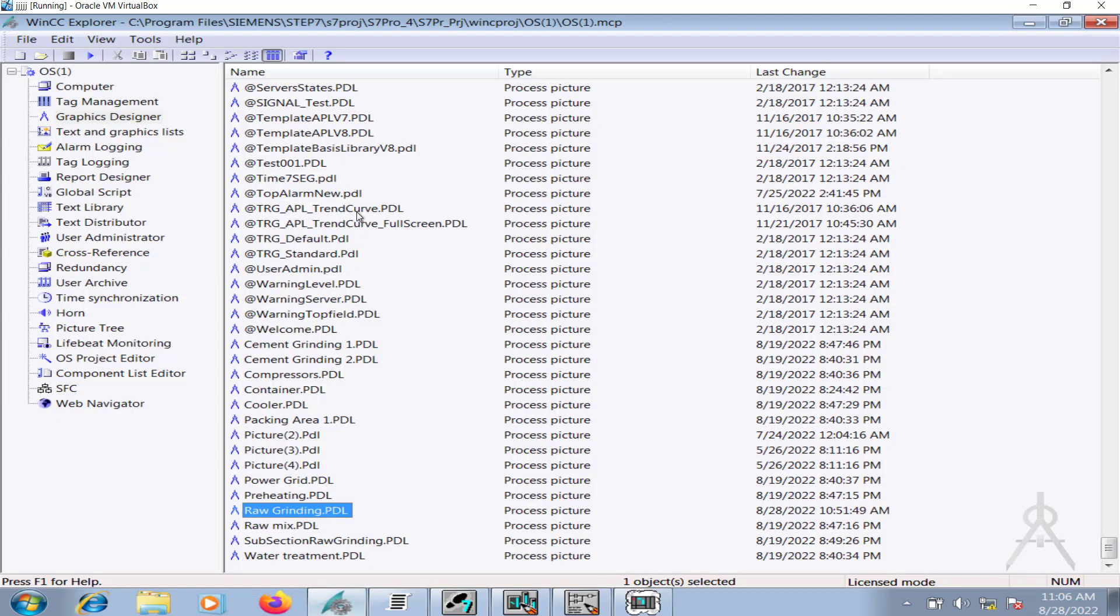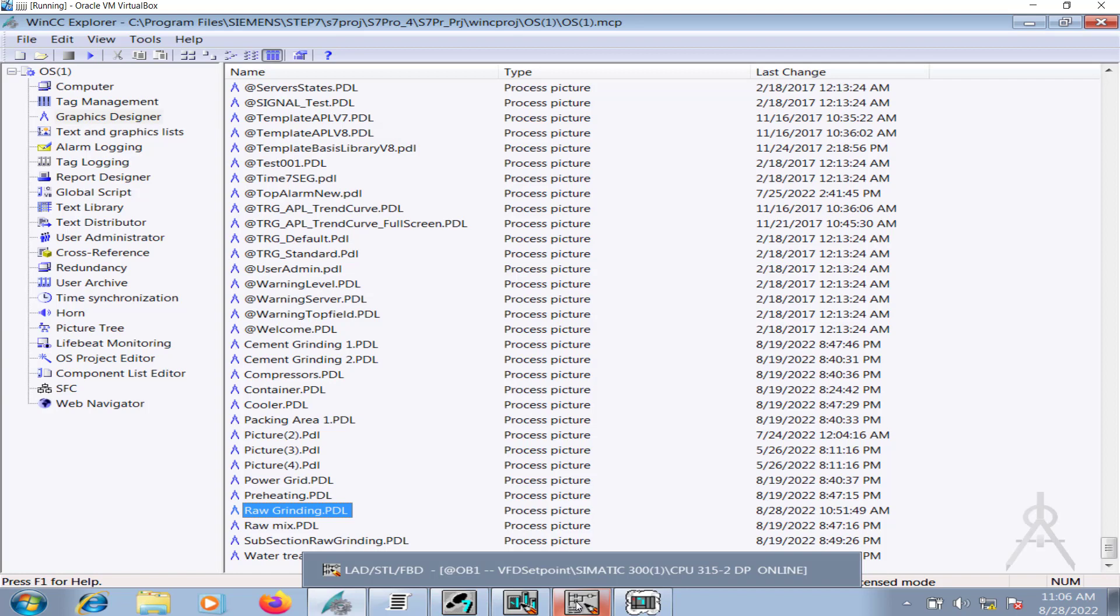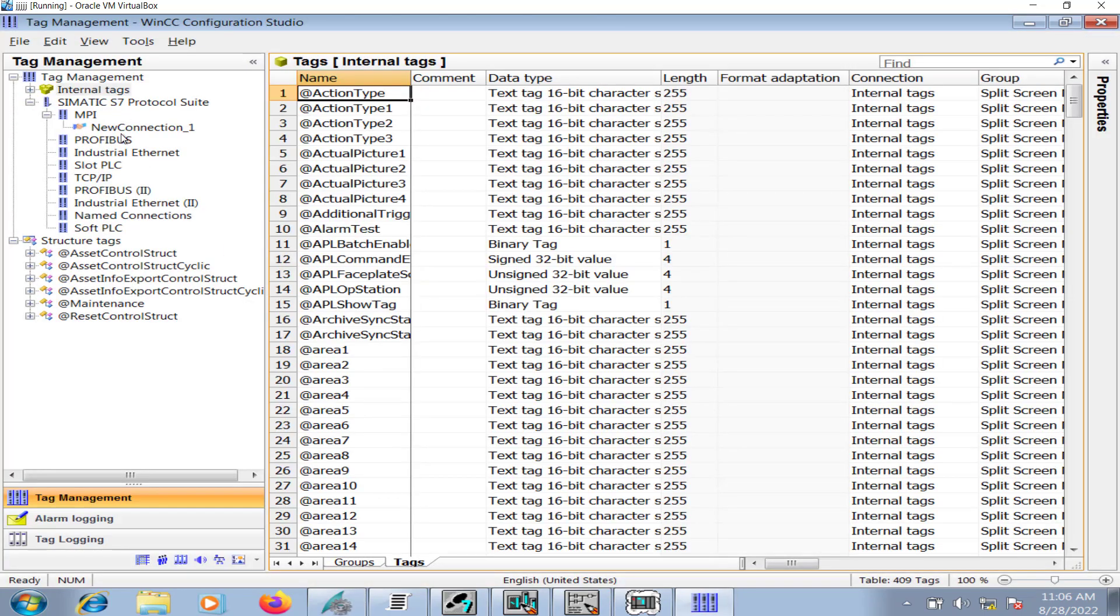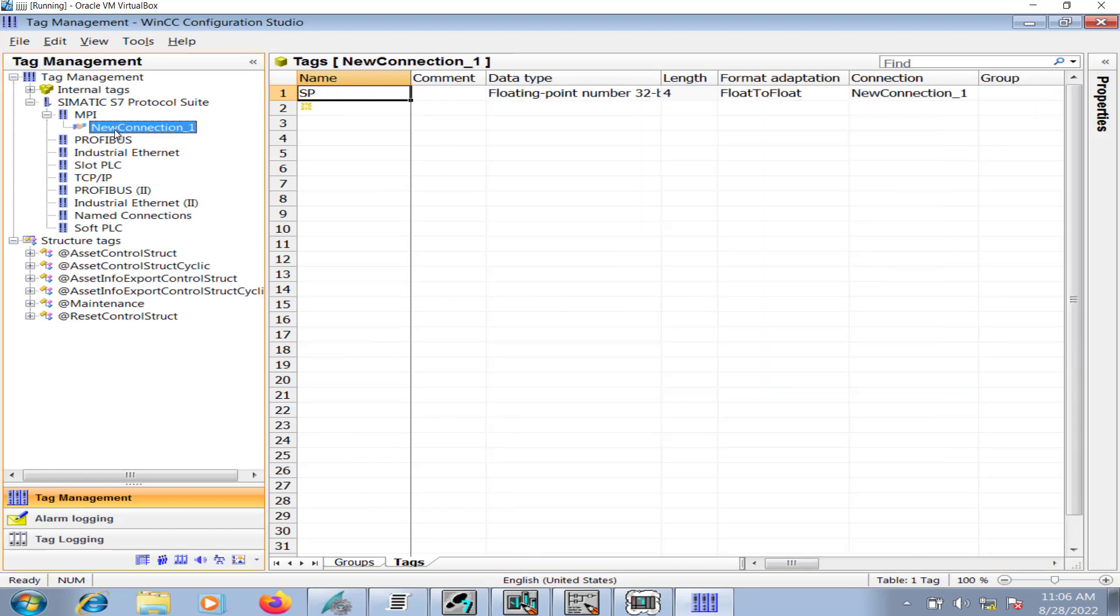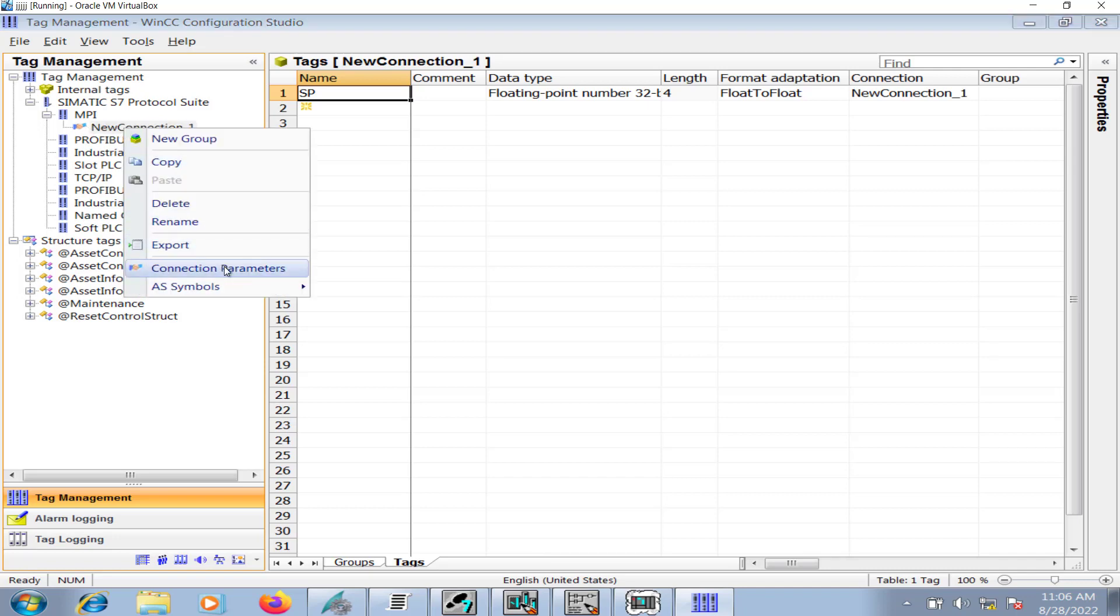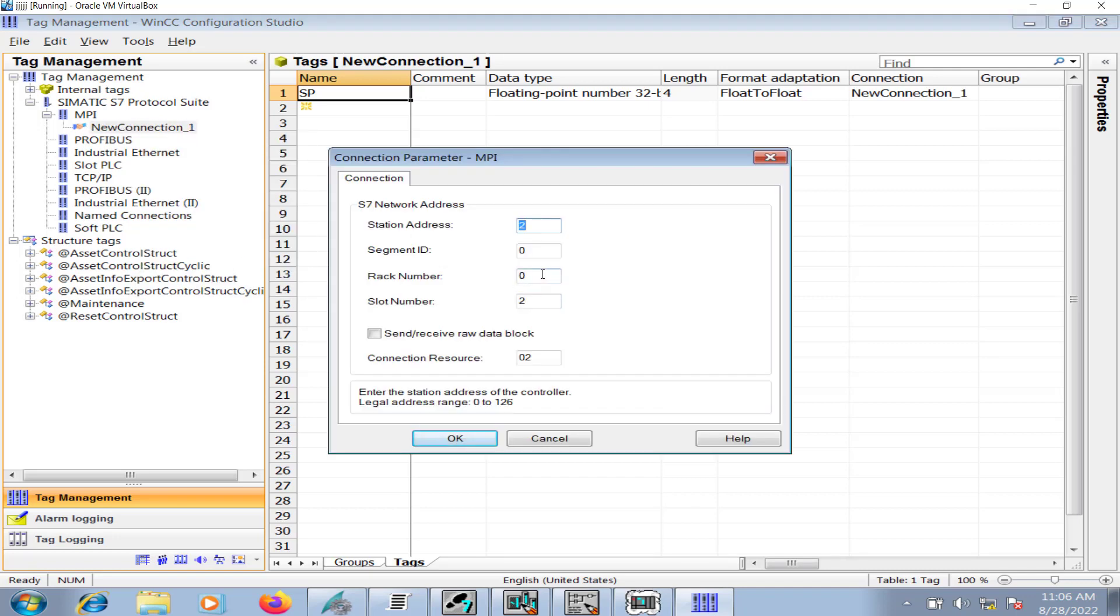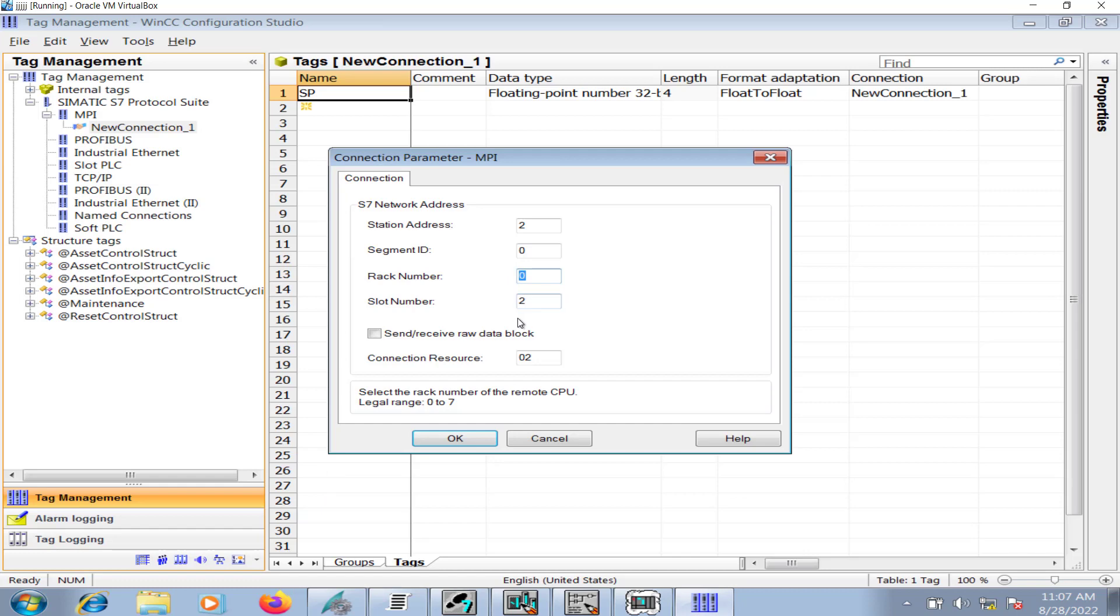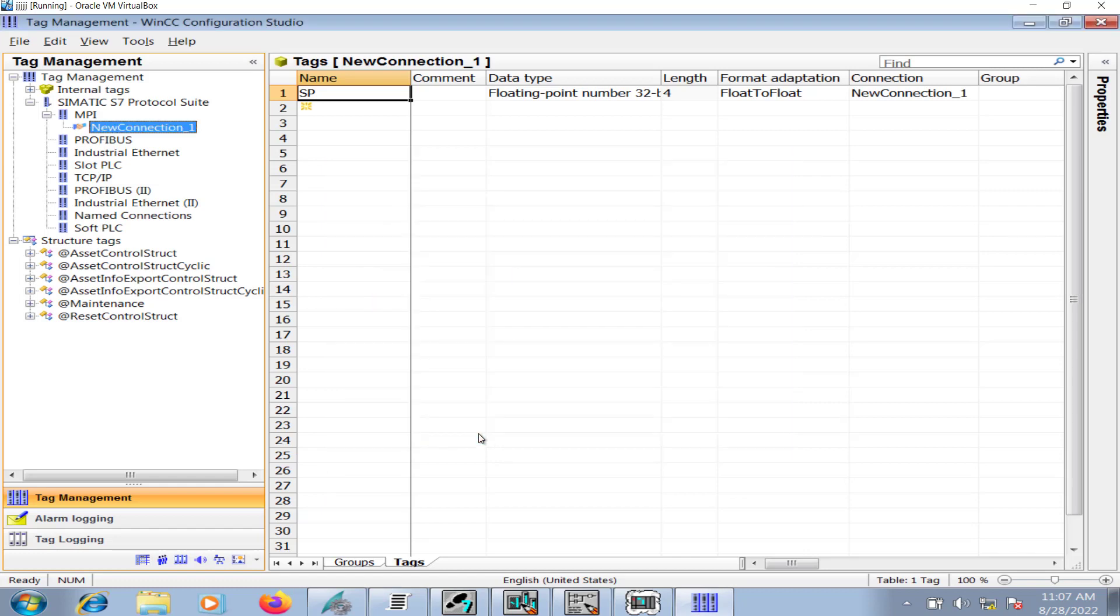First I will establish a connection between the HMI, that is the WinCC HMI project and the Simatic PLC, that is S7-300 315-2DP in this case. For that I have to go to the tag management. You can go to the MPI section, create new connection. Once new connection is created, go to the connection parameters. Over here you will insert rack number 0 because in hardware configuration the rack is 0 and slot 2 has the CPU. That's it, your configuration is made for the connection between HMI and Simatic PLC.